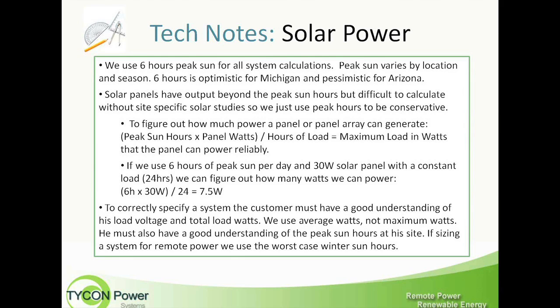To figure out how much power a panel or panel array can generate, you take the peak sun hours times the panel watts divided by the hours of load, and that equals the maximum load in watts the panel can power. For example: six hours times 30 watts divided by 24 equals 7.5 watts.